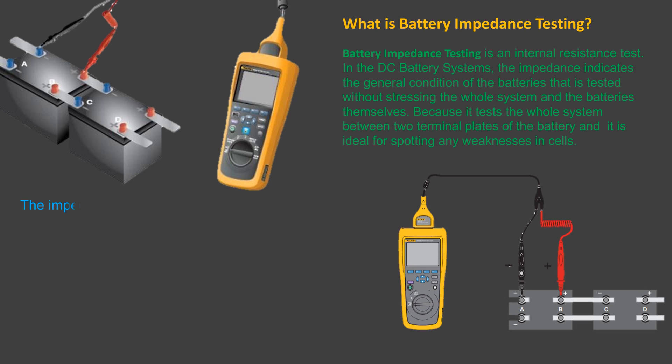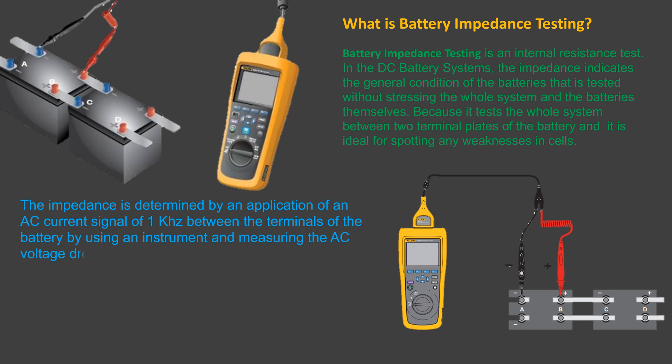The impedance is determined by application of an AC current signal of 1 kHz between the terminals of the battery by using an instrument and measuring the AC voltage drop across the battery, and then calculating the impedance by use of Ohm's law.